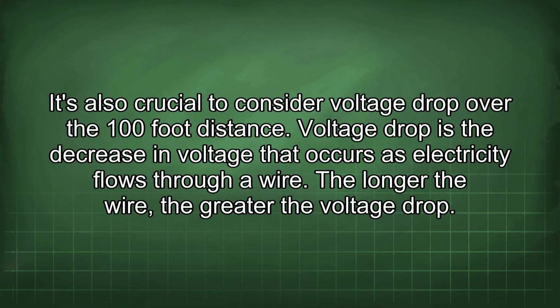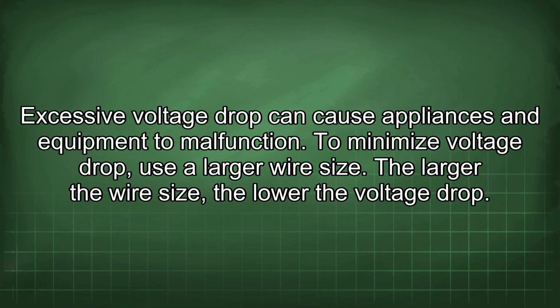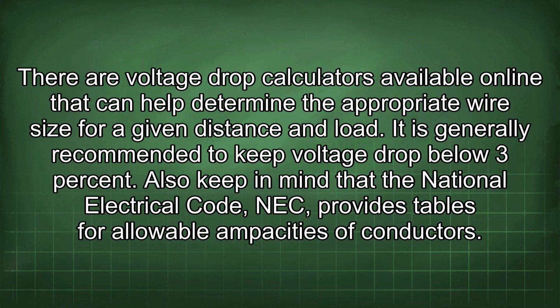It's also crucial to consider voltage drop over the 100-foot distance. Voltage drop is the decrease in voltage that occurs as electricity flows through a wire. The longer the wire, the greater the voltage drop. Excessive voltage drop can cause appliances and equipment to malfunction. To minimize voltage drop, use a larger wire size. The larger the wire size, the lower the voltage drop. There are voltage drop calculators available online that can help determine the appropriate wire size for a given distance and load. It is generally recommended to keep voltage drop below 3%.